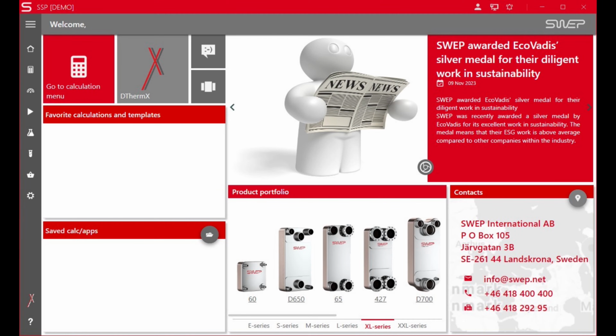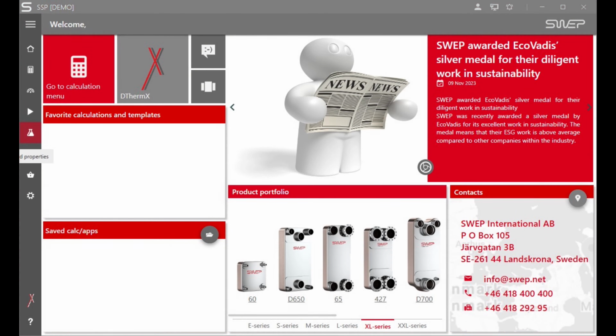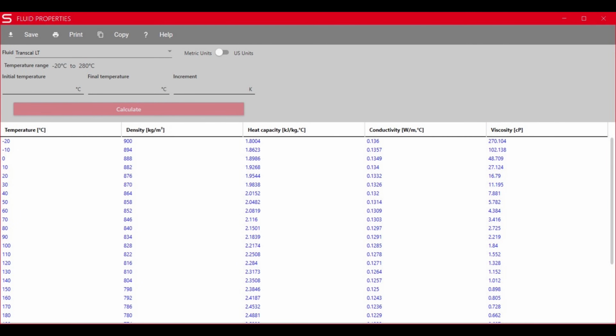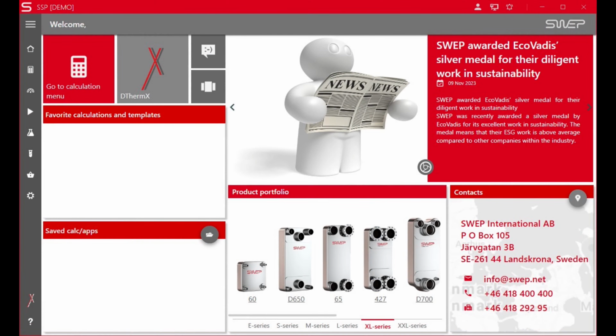And the first step is to set up the software with the right fluid property data. Now, the SSP software comes with a fairly expansive library of many industrial fluids, but dielectric ASIC cooling oil isn't one of them. I looked through the SSP library, and there is a listing for something called Transcal LT, which has properties fairly close to dielectric fluid. If you don't have the detailed data for your dielectric fluid, you can use this and you'll get fairly close. But if you do have the material properties for your dielectric fluid, you can create your own fluid data file to use within the tool.